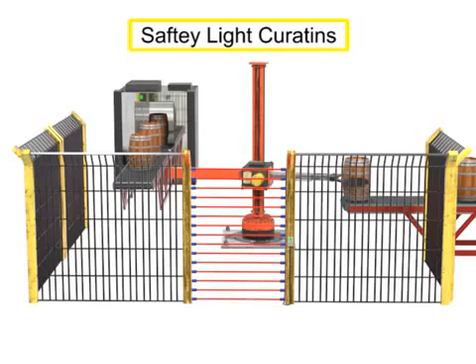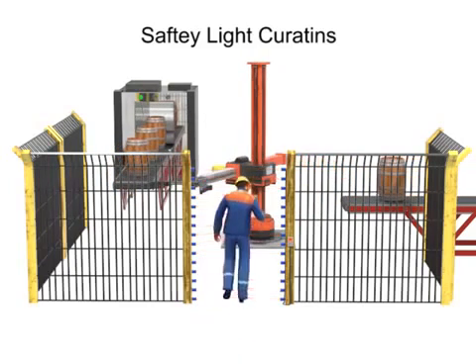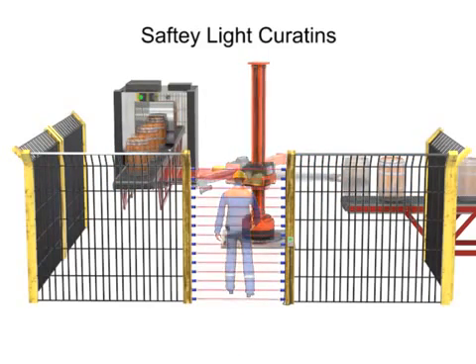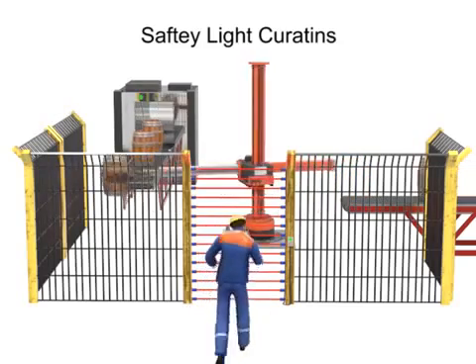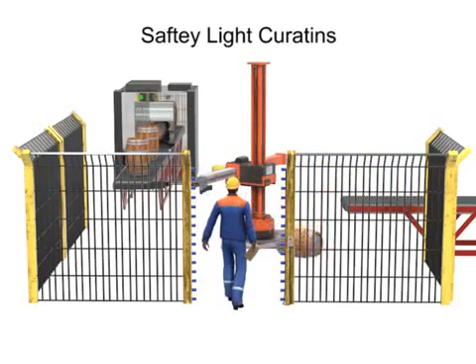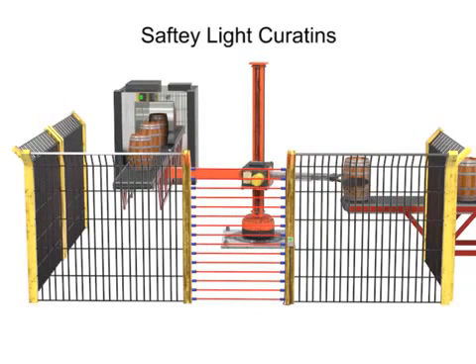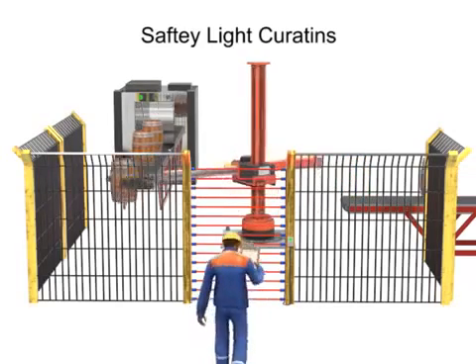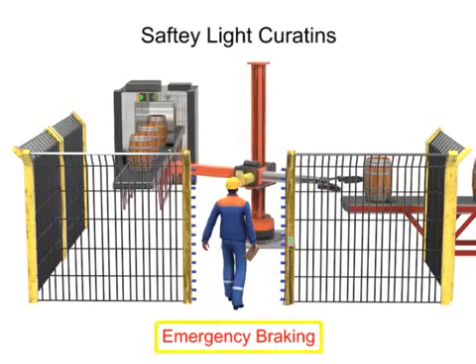Safety light curtains are another type of presence sensing device. When a person enters the work envelope, the light beam is interrupted, which sends a signal to the robot. For certain work scenarios, sudden stops could cause the work to become uncontained, as objects may continue to move even after the robot stops. In these cases, emergency braking is used in lieu of completely stopping, so the robot slows down work and does not stop suddenly.